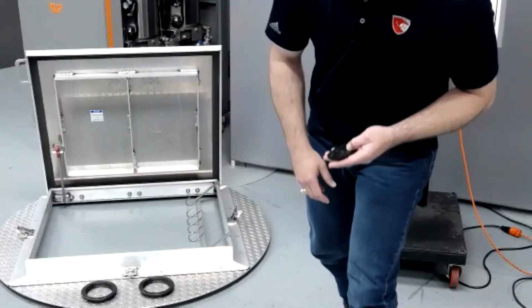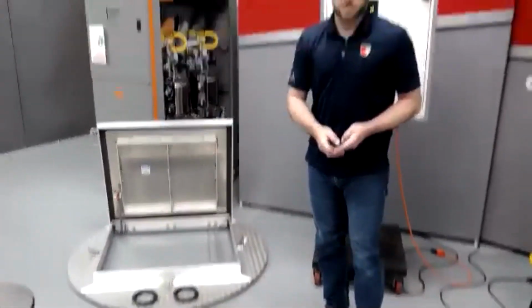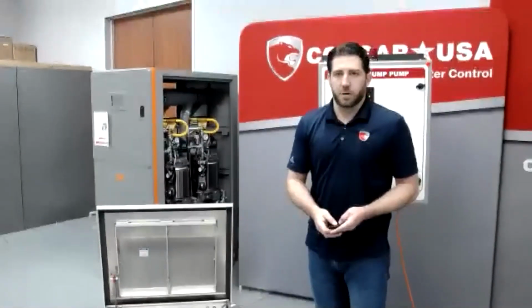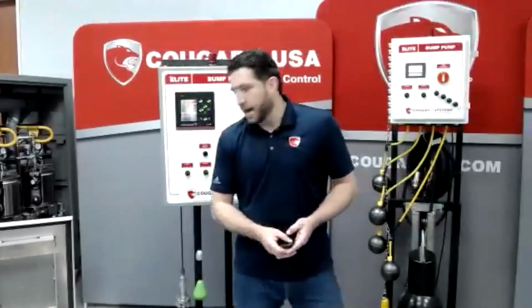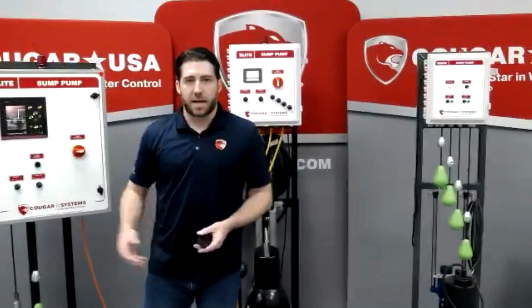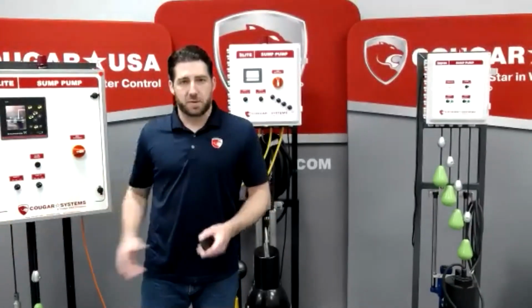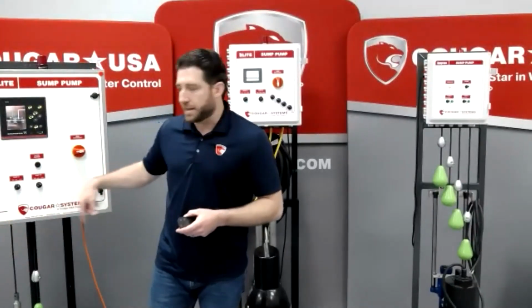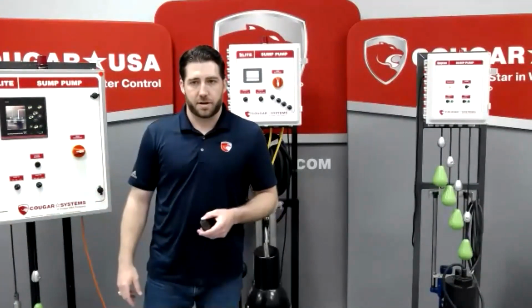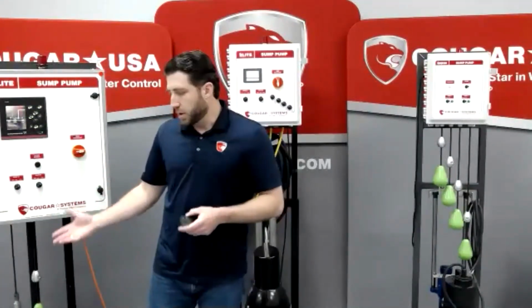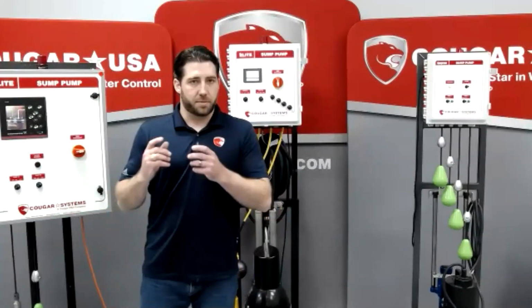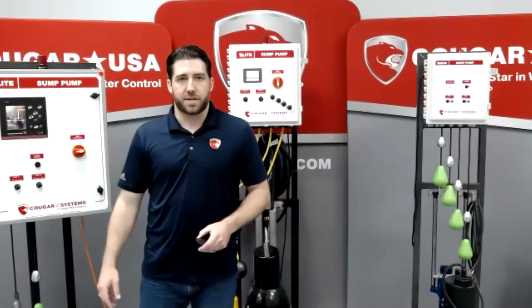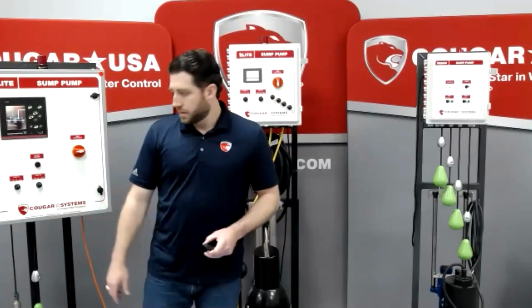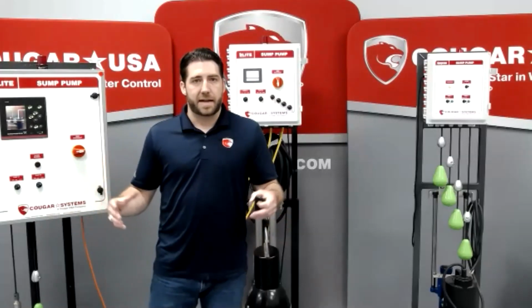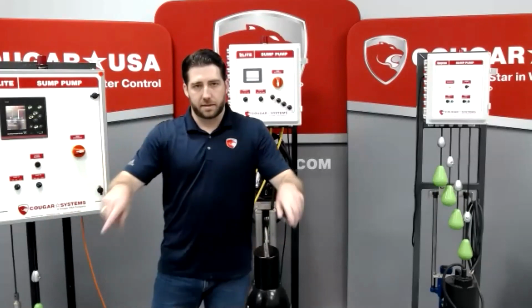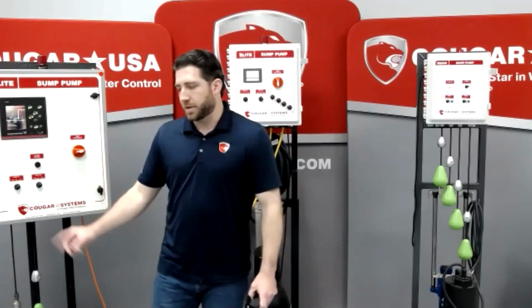Can you touch base on the pump removal systems? So some of these are demos, and they have large hatches on there. But typically we would size the hatch with enough room for the piping penetrations to come through around the hatch, as well as the conduit connections. So in most of our applications, all the piping is coming right through the covers. It's not going out through the sides. So typically we would size the hatch to be just big enough for the pumps to make it out, and then leave enough room for the piping penetrations through the rest of the cover.